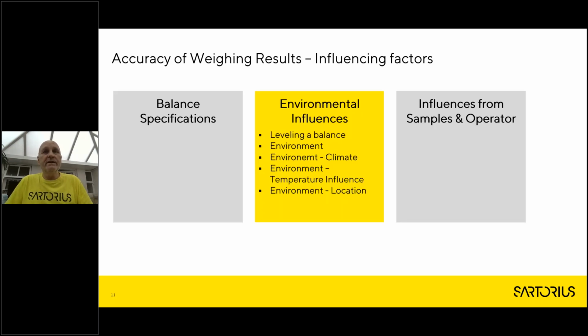So now, having looked at the balance specifications, one thing just to say, those 4 balance specifications which we've looked at will combine to produce a measurement uncertainty. So we take into consideration all of those 4 errors, and then we can actually quantify any measurement uncertainty by combining them together in the root mean squared effect. So moving on to environmental influences, these are things which we can and cannot control, and if we work hard to mitigate these, we can reduce the overall error on the balance.